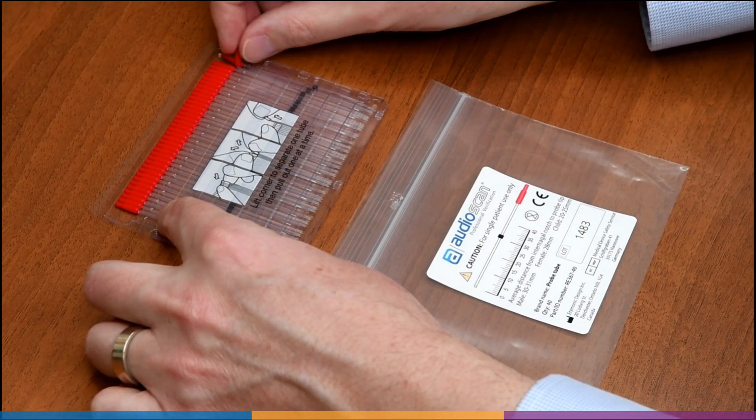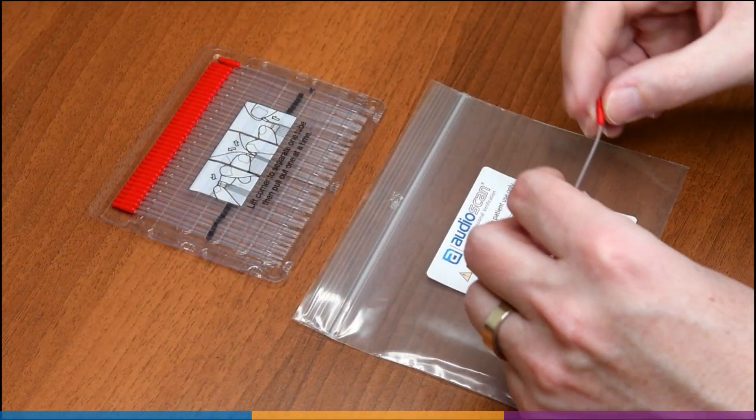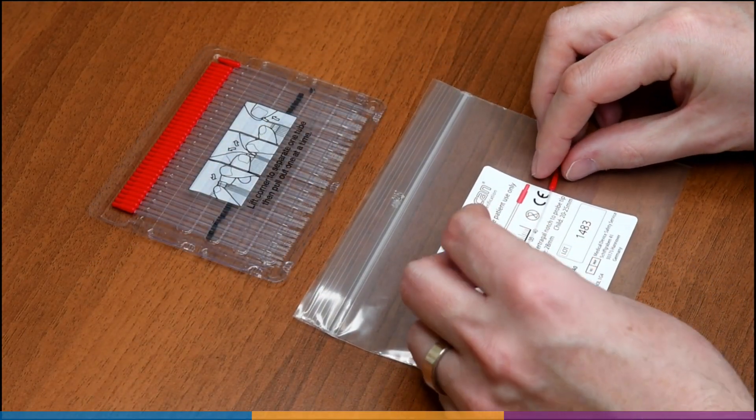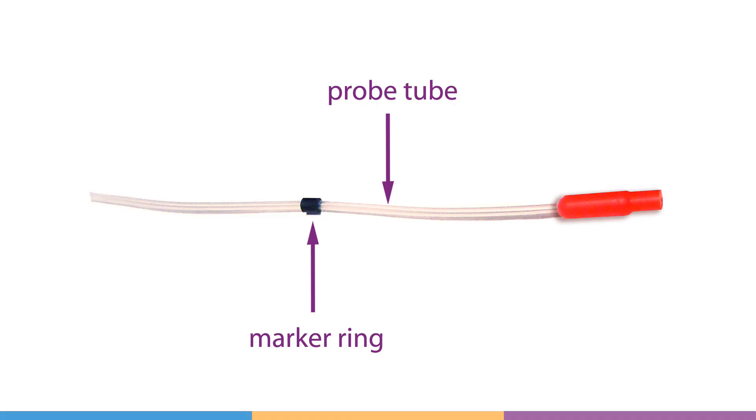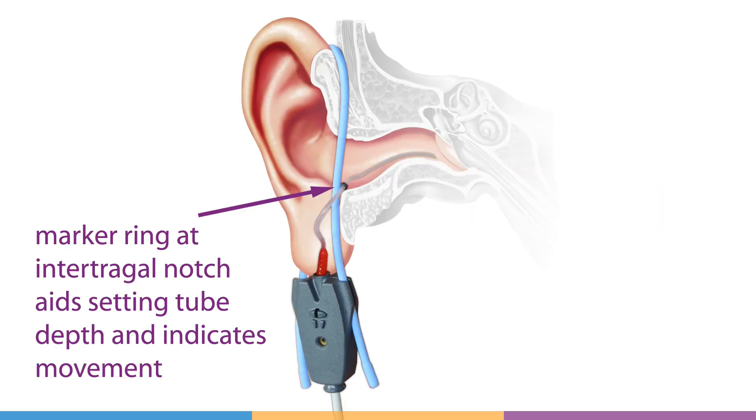Using a new probe tube, set the black marker ring to the average depth indicated on the probe tube packaging. While a ring is not required for positioning with ProbeGuide, it can help show inadvertent movement of the probe tube during later hearing instrument or foam tip insertion.